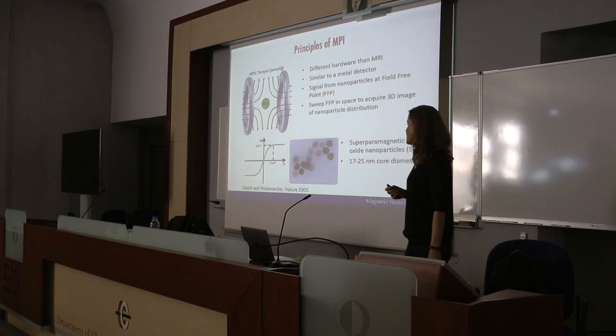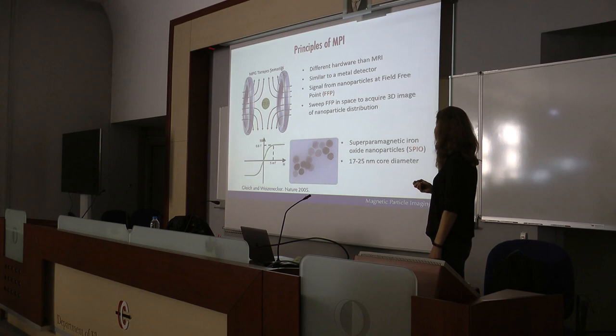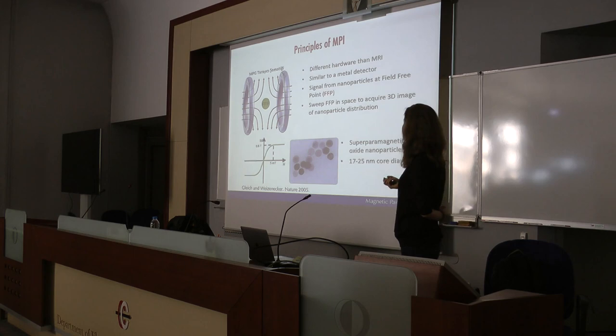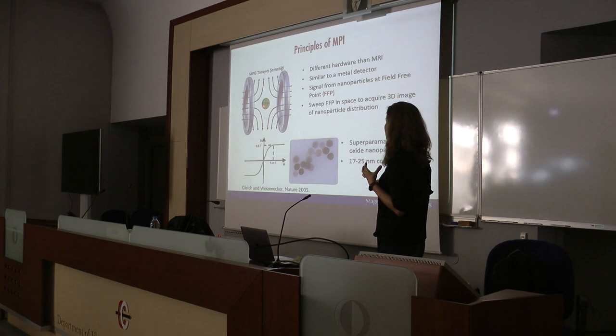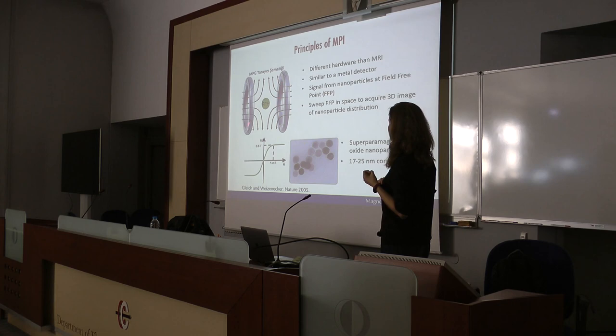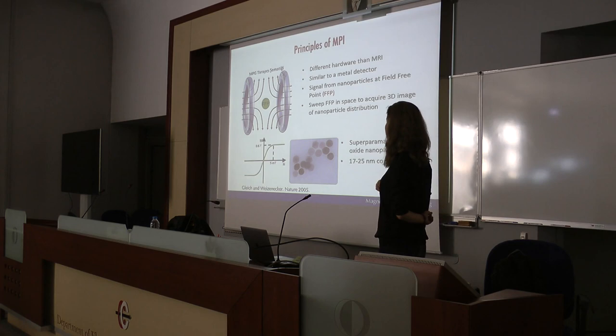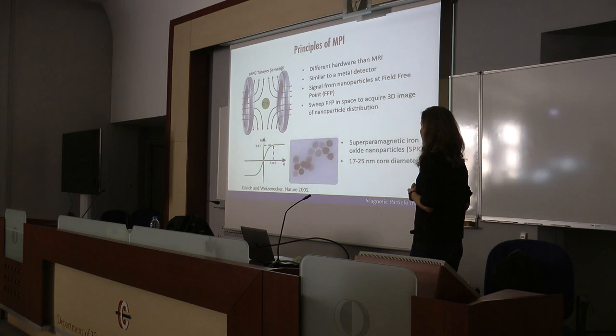I want to give a brief introduction to the principles of MPI. This is a schematic of a typical MPI scanner. The hardware is different from MRI — in MRI we have a large homogeneous static magnetic field, whereas in MPI we have a gradient-type magnetic field that ramps up linearly from one side of the scanner to the other. You can imagine two magnets facing each other with the same poles, creating a field-free point at the center of the scanner. We take signals only from nanoparticles at the field-free point, and by sweeping this field-free point in space we acquire 3D images of the nanoparticle distribution.